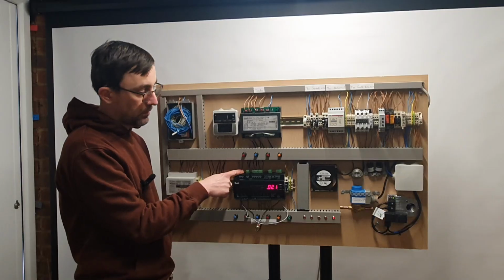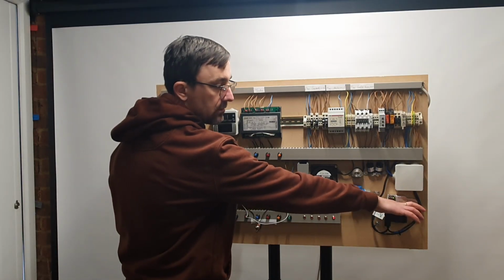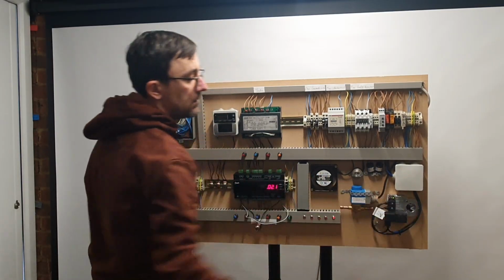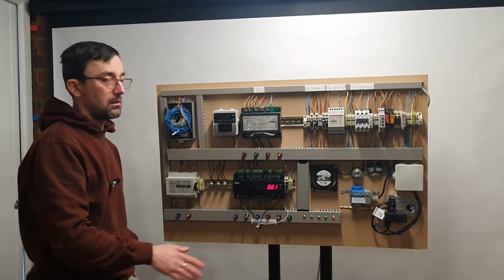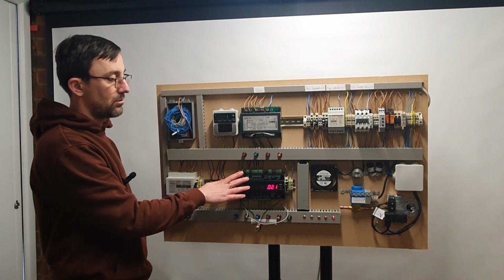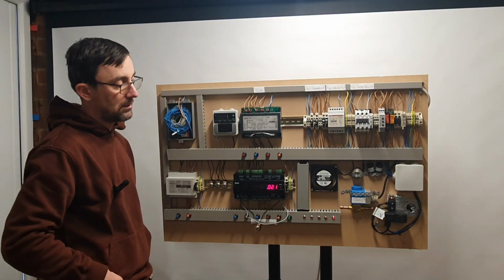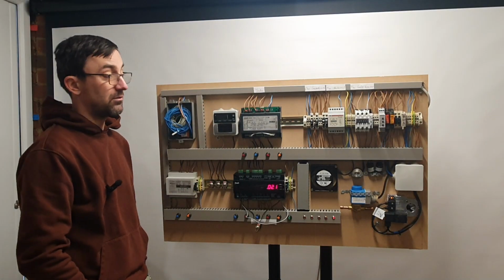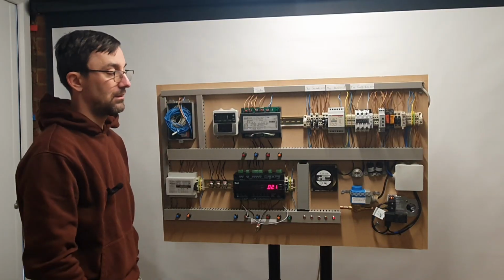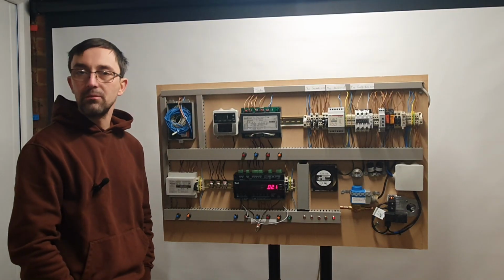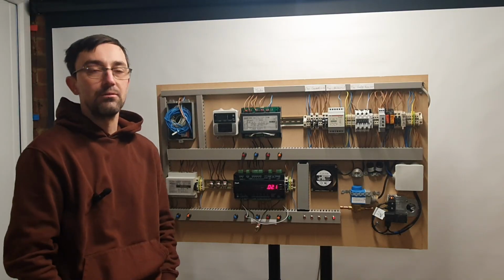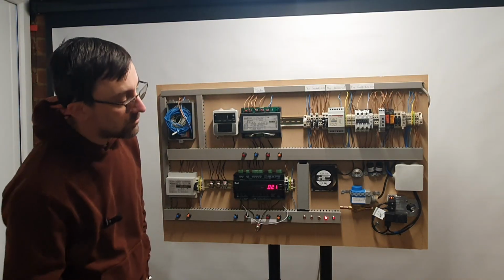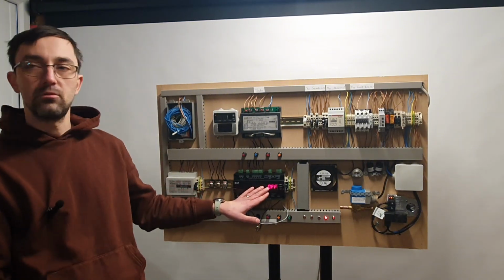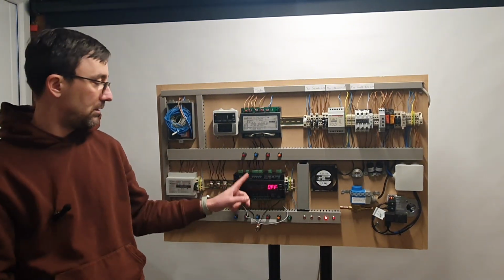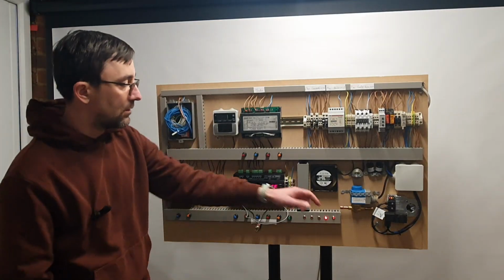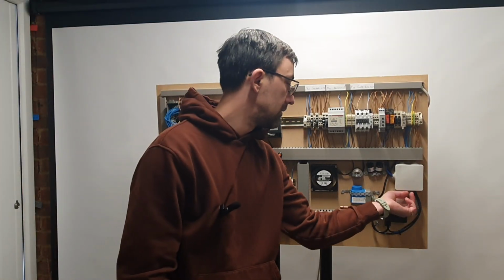Okay, digital input number 2 is a stop refrigeration alarm. And the way that I configured it is like a main switch, because I want the controller to stop doing what it's doing. There's no point in running the fans if the compressor is not working. I mean by that, tripped on high pressure or low pressure. It's not going to do anything anyway. So I just wait for the red light and you stop. And it also stopped my fan. So that's working correctly. So let's just put this back to on.